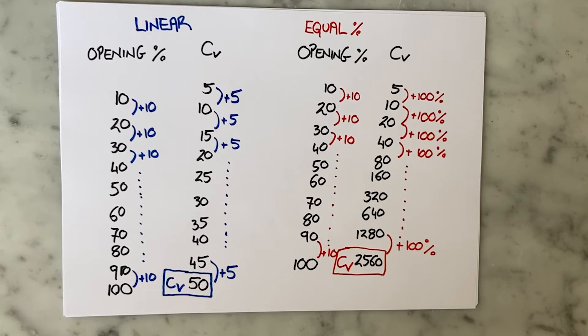This is the difference between a linear and an equal percentage valve characteristic. For a given step change in valve opening, a linear valve CV increases by the same amount, while an equal percentage valve CV increases by the same percentage. And that's where it gets its name.